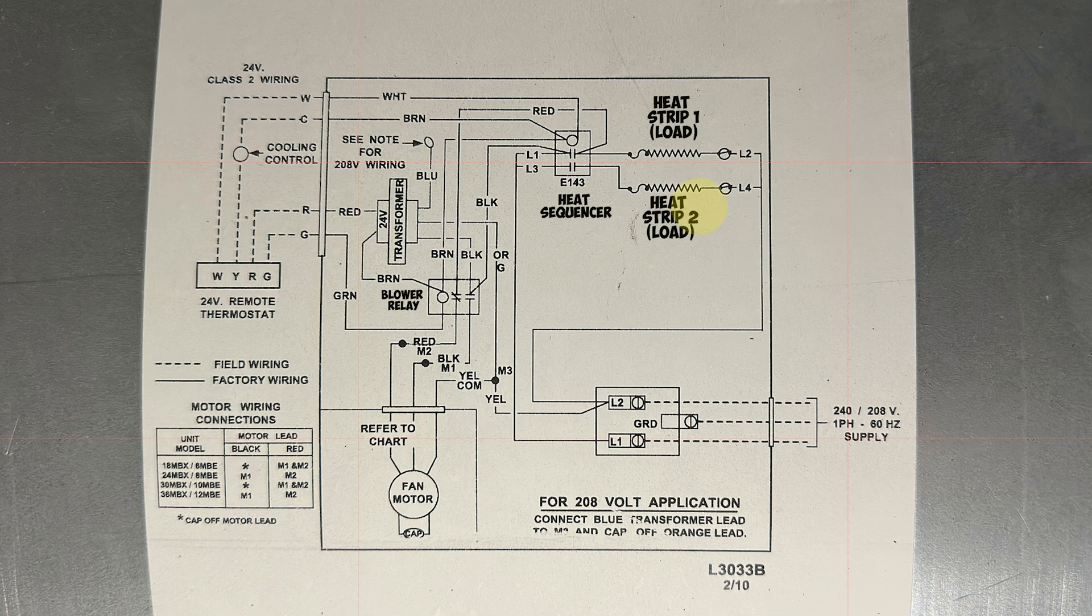And also over here is when red or black, let's say when M1 and common are going to the motor, the motor is going to run. When M2 and common are going to the motor, the motor is going to run. But only one of them can go to the motor at one time. And I'll try to explain this so that we can see what's going on and how I determined just off doing those tests I just did, that the heat sequencer is bad.